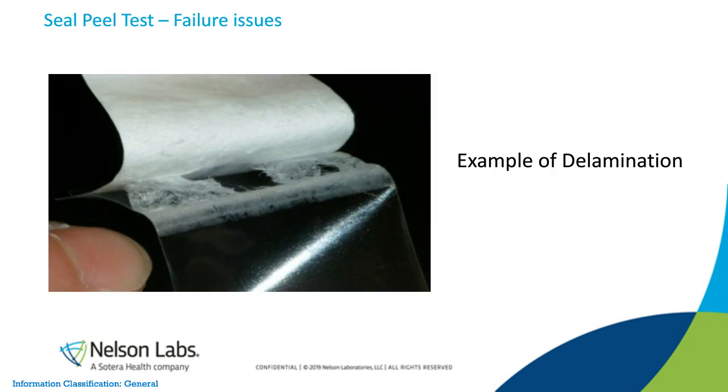When the oversealing is less severe, there can be delamination or fiber tear. As you can see in this picture, instead of peeling open cleanly, some of the Tyvek material did not release. Delamination makes aseptic presentation harder. It's difficult to open the package, and the separating fibers could be releasing organisms that might be trapped in those fibers. So the take-home message here is that when sealing, don't go for too cold or too hot. Like Goldilocks, you want to be just right.